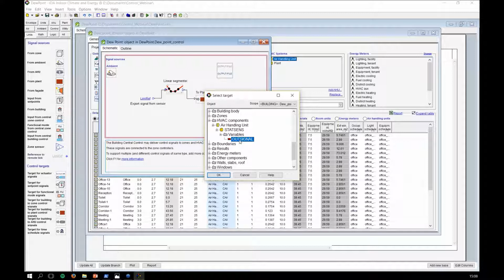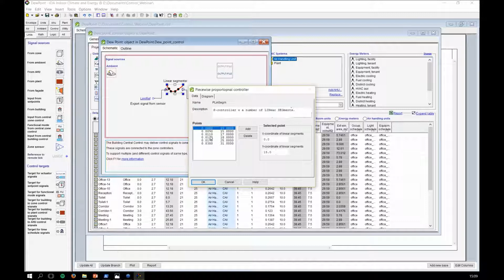What am I doing with this sensor? I'm feeding it to a linear segmenter. Our control strategy is staying 1 degree above the dew point temperature. On the x-axis, it's not really clear here, you'll see the humidity ratio, and on the y-axis is the set point that I would like. I did it so that the minimum set point is 15. We don't want to go below that. And we go always 1 degree above dew point as the humidity ratio goes up.